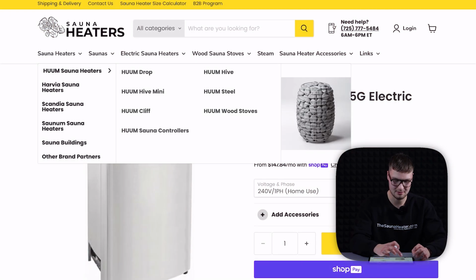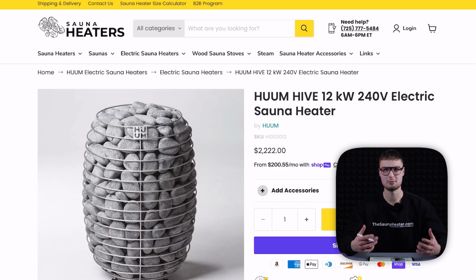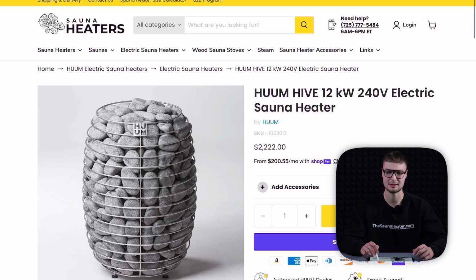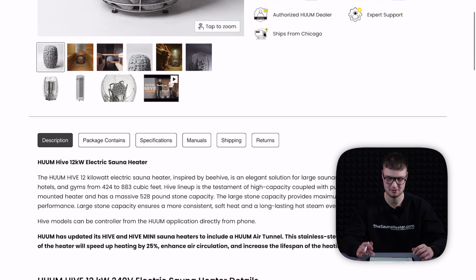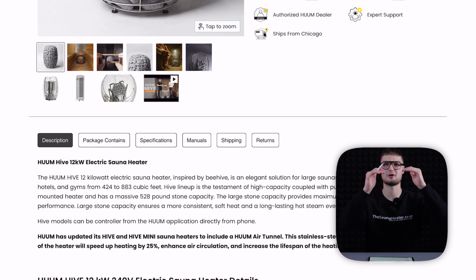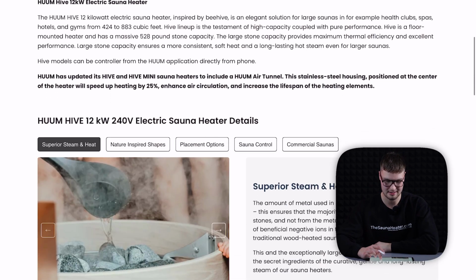Let's take a look at another model, HUUM Hive as an example. HUUM sauna heaters are always 240 volts one phase. You can see that directly on the title here. You can wire this with 208 volts one phase, but that will reduce the power output by 25%, so please take that into account.